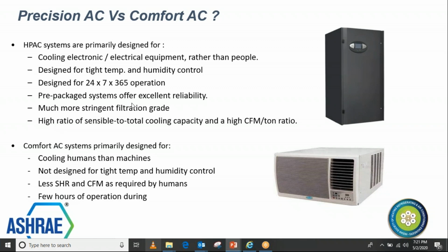And these are all complete pre-packaged systems. Why? Because these applications demand a high-end kind of uptime, with criticality built into the systems, and all components are built in one enclosure. You can see on the top right side a picture of a DX unit, which has all the systems like the evaporator coil, compressor, heater, humidifier, dehumidification cycle, fan, and controller, everything built inside this cabinet.